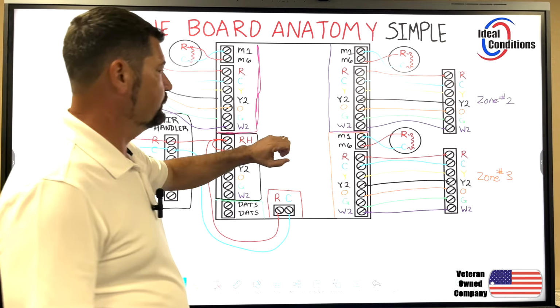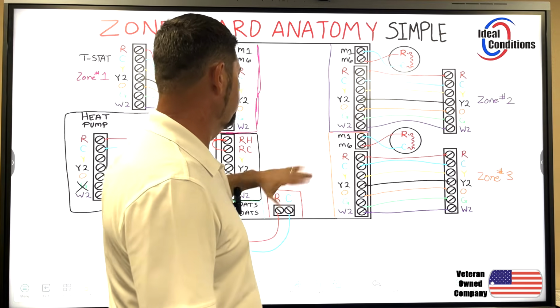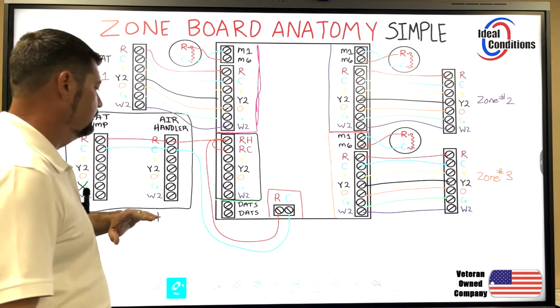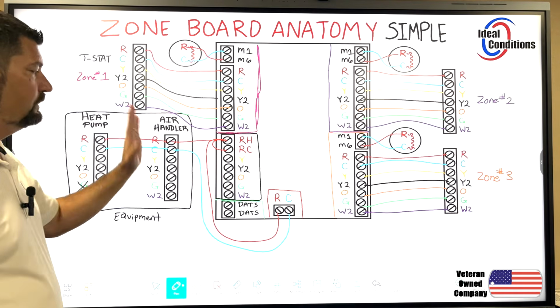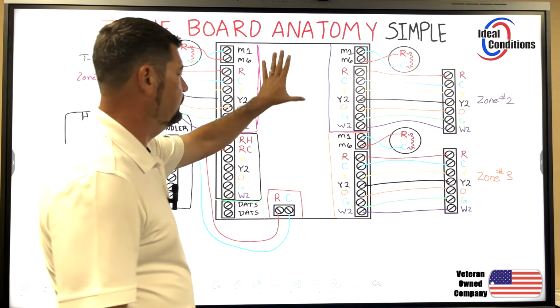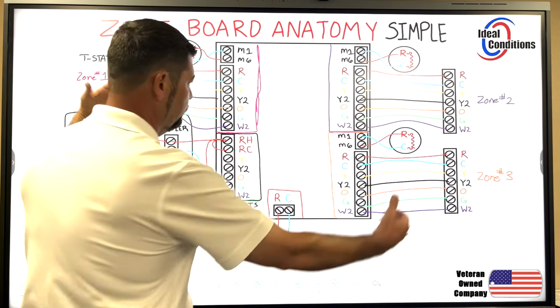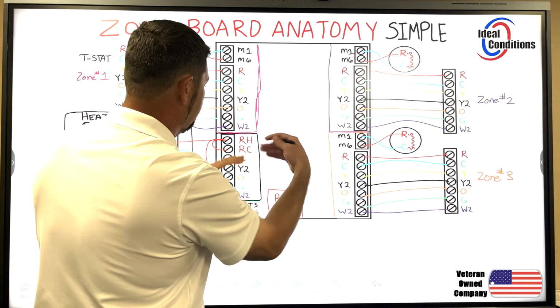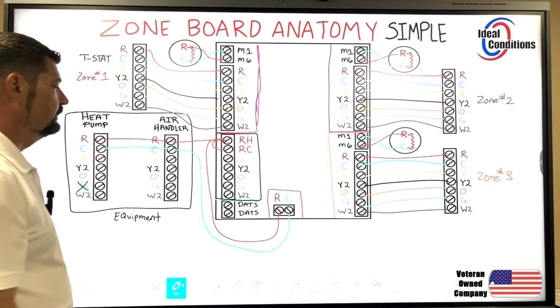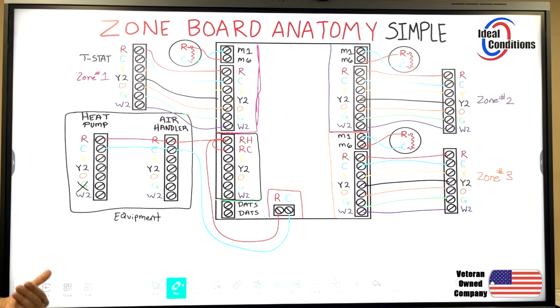This zone board will catch and know which mode to put it in, heat or cool, fan on, and which damper to close. That's the job of the zone board: take the incoming information and send it out according to demand and priority.